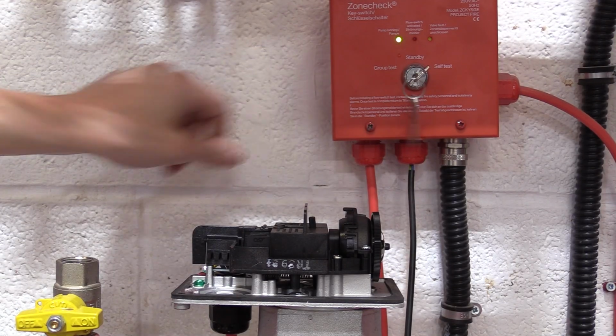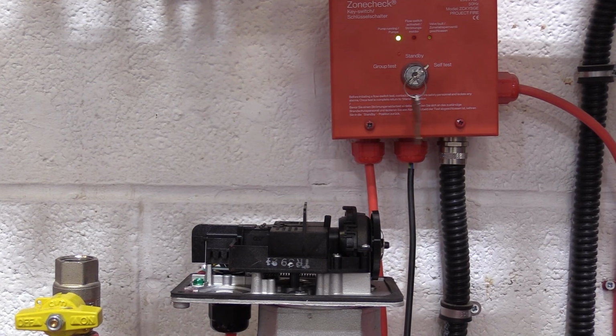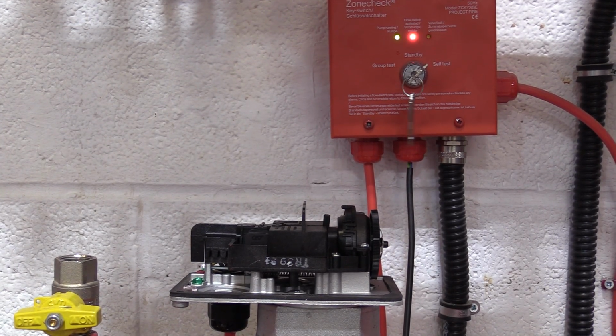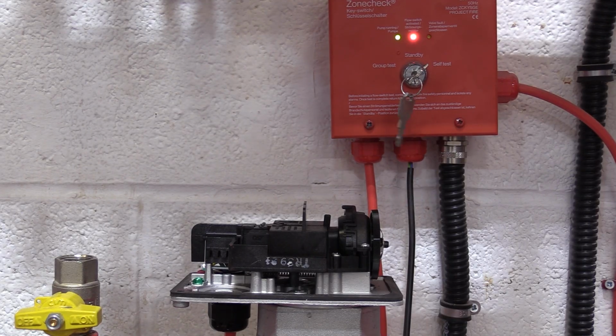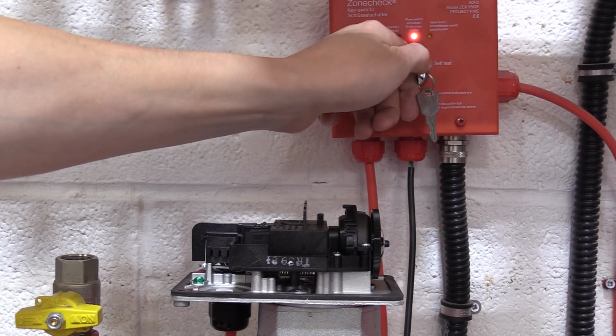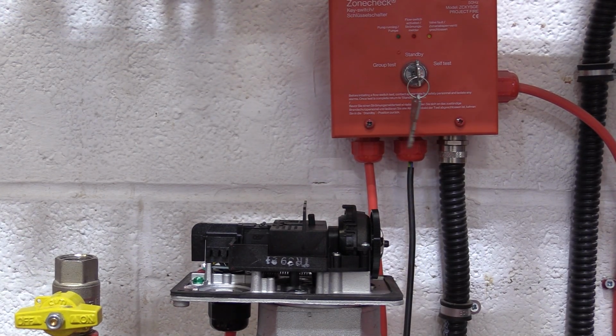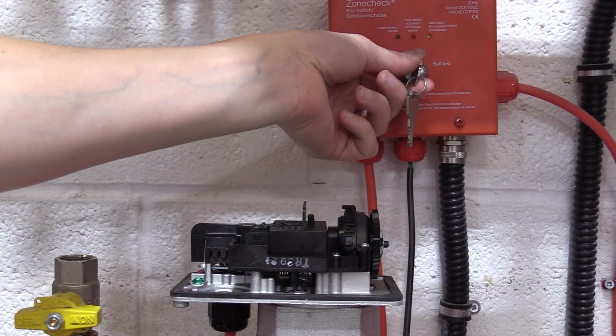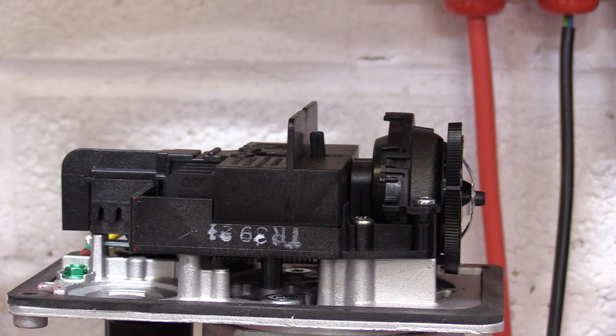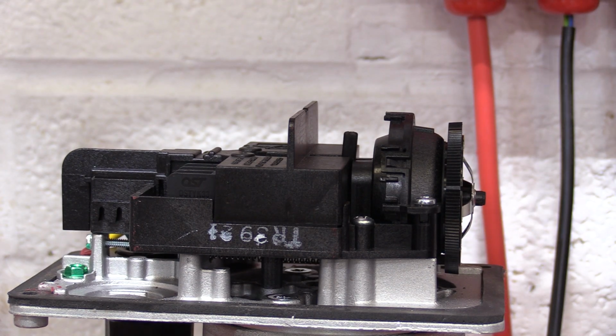With the pump running, look at the spring-loaded pin. Either one of these three things should happen. Number 1. The pin moves all the way to the end and an audible click can be heard. If this happens consistently, then the Zonecheck is working correctly and the issue is likely to be with signalling between the flow switch and the key switch, or the flow switch and the fire alarm panel.